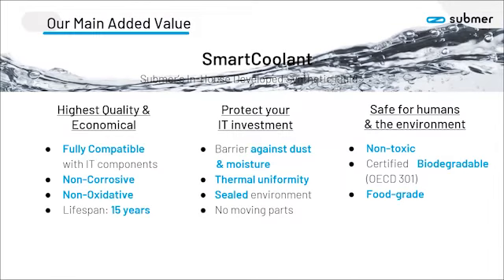It gives you a degree of thermal uniformity. In an air-cooled environment, the temperature of the equipment will swing a good 10 to 20 degrees centigrade routinely — memory and CPUs get busy, get hot, fans speed up and slow down. I don't get that in this environment; I stay within about 5 degrees centigrade no matter how much work the systems are doing. That thermal uniformity makes everything more reliable and really extends the life of the equipment.